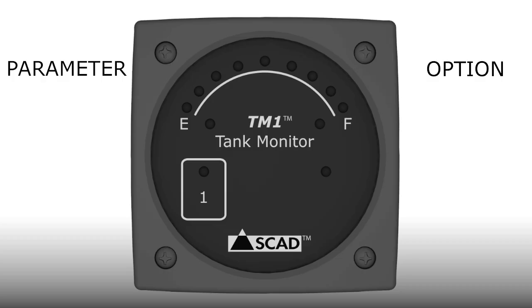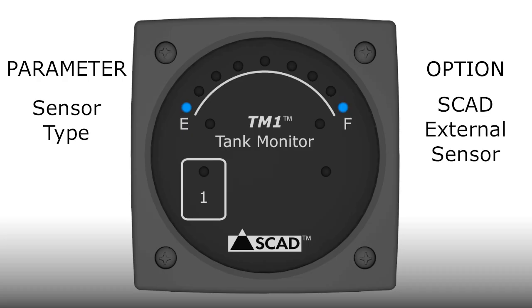The first parameter in the sequence is sensor type. It's indicated by the E light. The first sensor option is the SCAD external sensor. This is the default setting, so the light will be constant unless someone previously set a different option. If you want to keep the option, don't touch the pad and wait for the monitor to move to the next option. The second option is for the SCAD internal sensor.